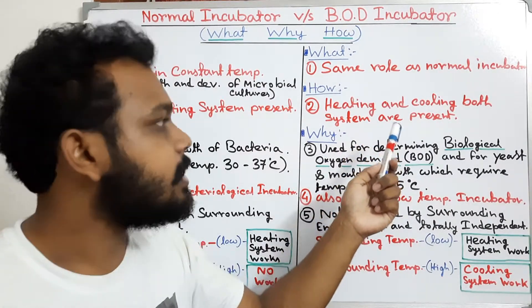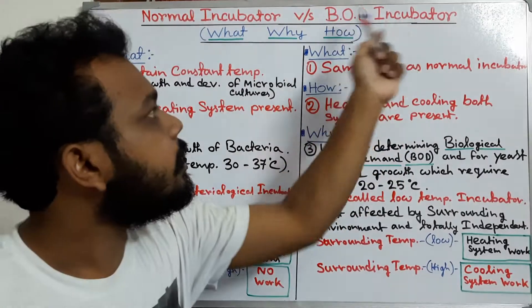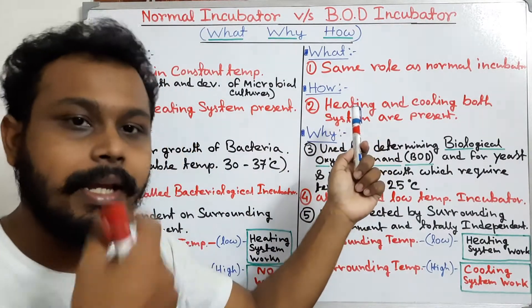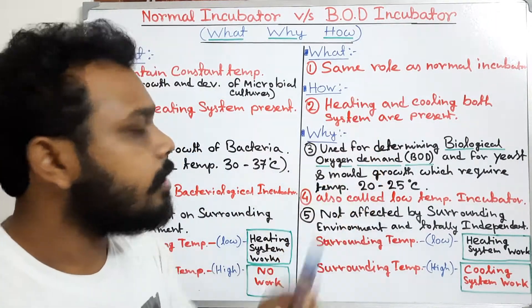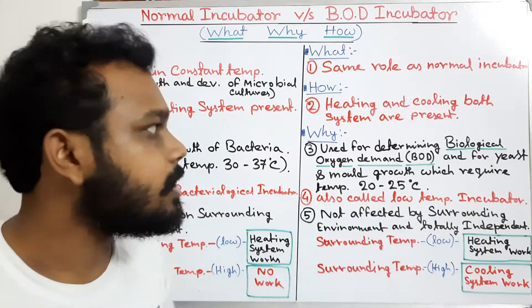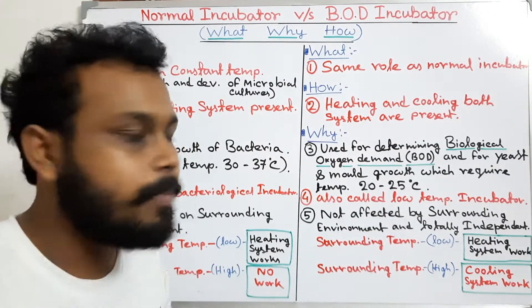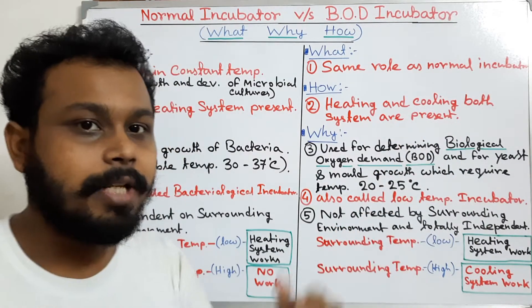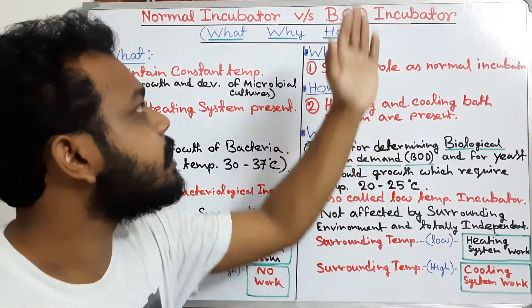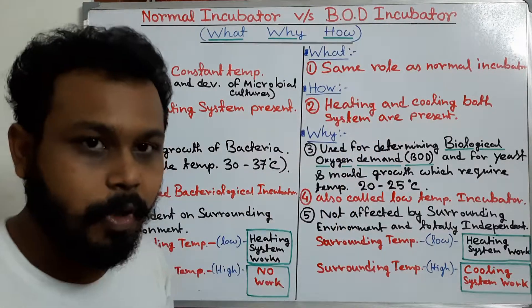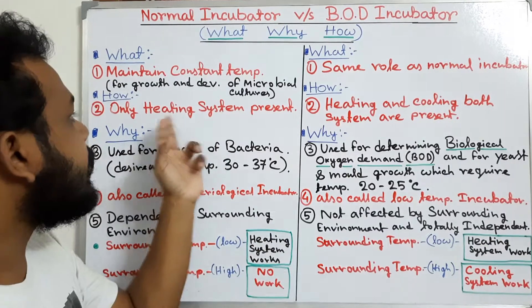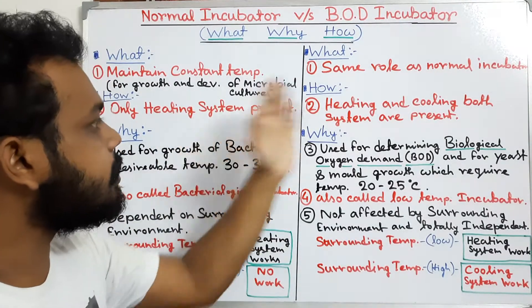The BOD incubator has a heating system that can achieve temperatures higher than room temperature, and also a cooling system that can maintain temperatures lower than room temperature. So both systems are present in the BOD incubator, but in the normal incubator only the heating system is present. That is the main difference between them.